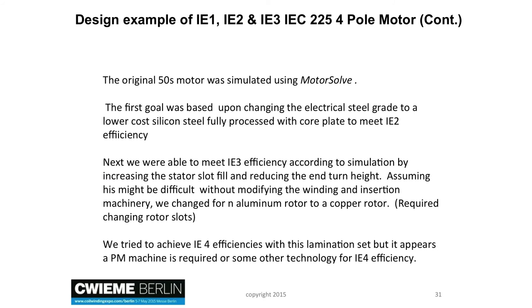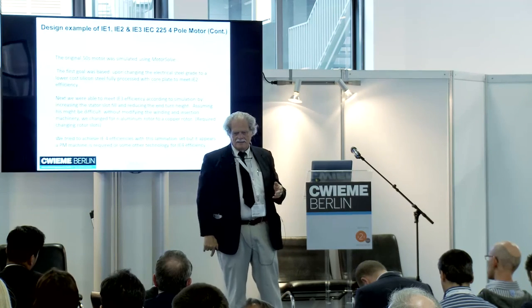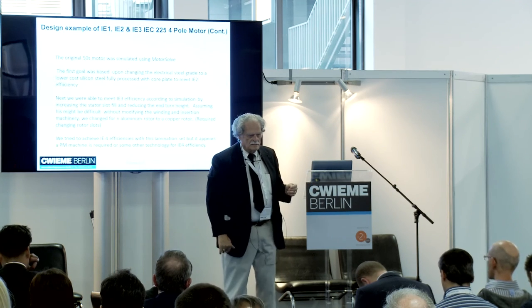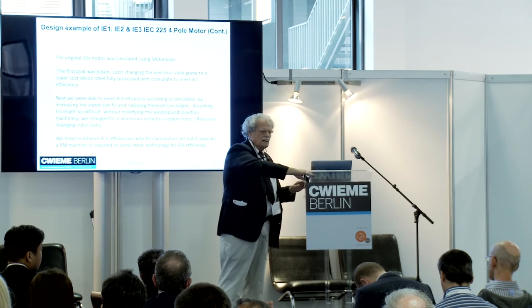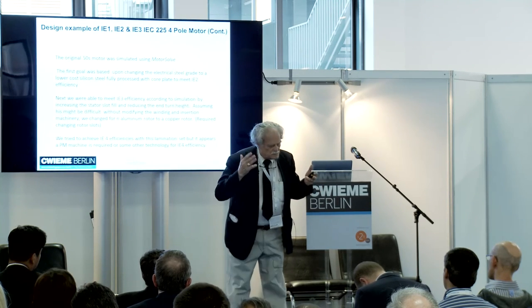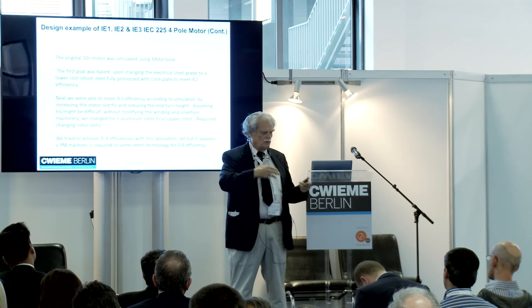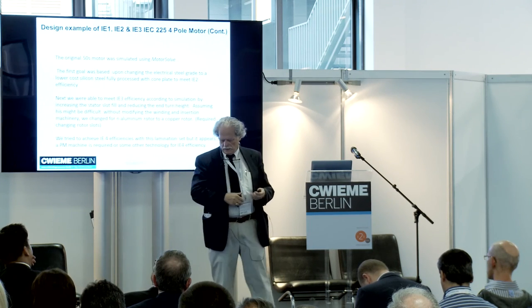General Motors has a patent on it. Hitachi has a patent on it. But they're easy to get around. All you got to do is change the angle of the tool and the speed and the feed, and you get around the patent. But there's companies that are exhibiting here that do that. Okay? So that's a fantastic technology for getting a copper rotor. Otherwise, if you're going to fabricate them the old-fashioned way, now the copper rotor induction motor costs almost as much as the PM synchronous machine. You see? So either die casting or stir welding can mitigate that cost delta somewhat.